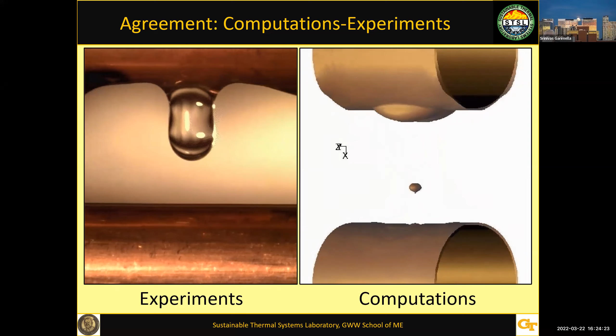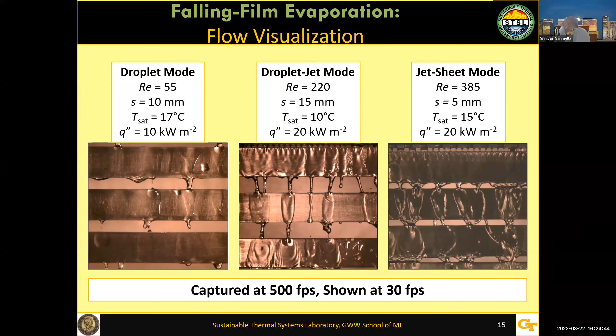We've done similar work on evaporators. These are rectangular tubes increasingly used in industry. You don't want the film to be so thick that it creates additional resistance, so we've come up with designs that avoid that. Sometimes it's also difficult to distribute the flow properly, so we've developed nice distribution devices so the entire surface is utilized.